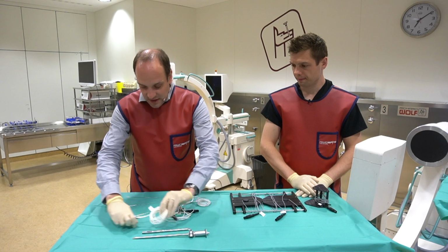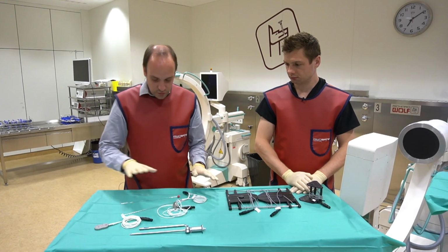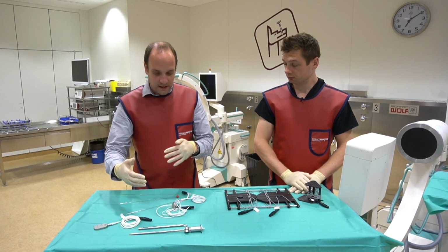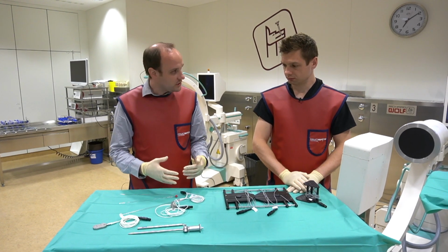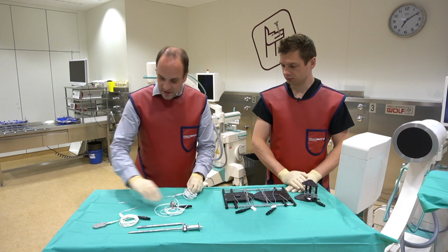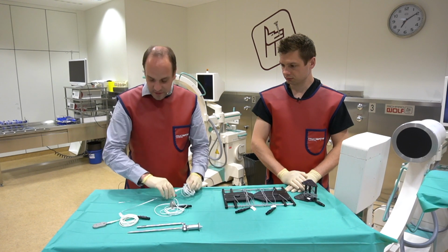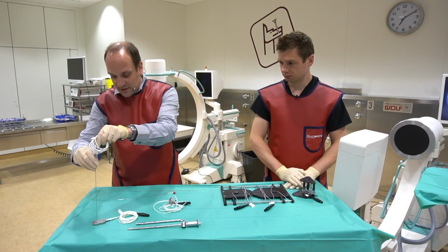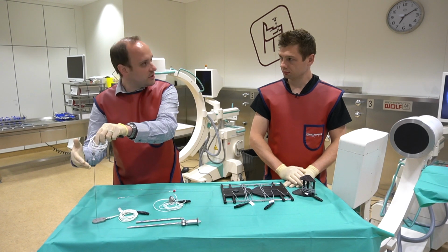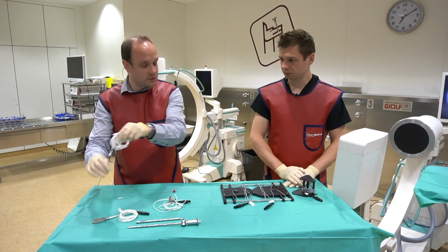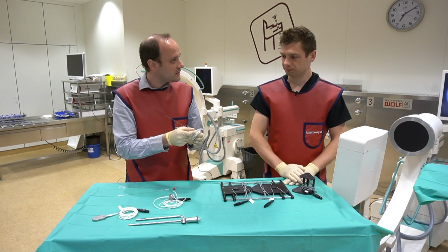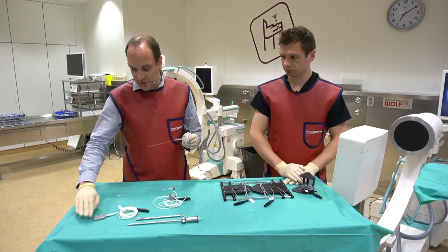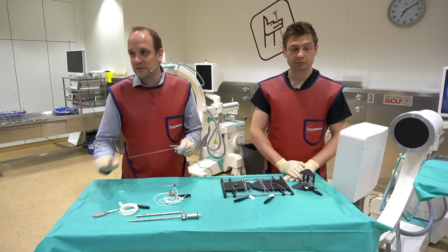Yeah. And one more item that you see here, there's a sensor inside as well. This is the multipad, and it's necessary to, if we have a tool change, we need to know which tool we are using. So this has to be in the field of the field generator. We place the needle on top like this. And once we do that, the system knows which tool you're using, because the relative position of the sensors that are inside the needle, they have a certain position to the plane of the multipad.